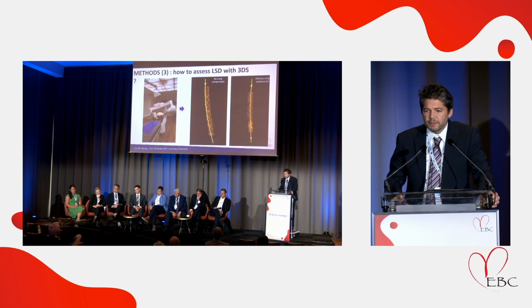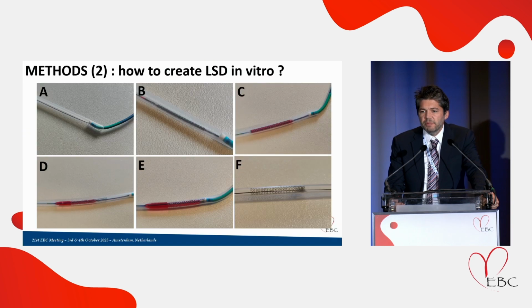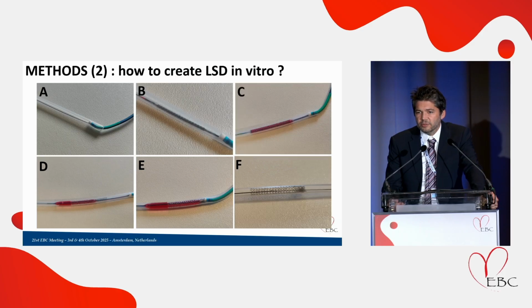That's how we created the LSD in vitro. You see, it's not rocket science. We implanted the stent into the silicone tube, inflated it, and then we pushed the balloon slightly over the stent, re-expanded, and then pushed on the guiding catheter to create this compression that you can see on panel F. I hope that it's not the kind of thing that we can do in the cath lab, but for the purpose of this in vitro trial, we really wanted to exaggerate the pitfall.